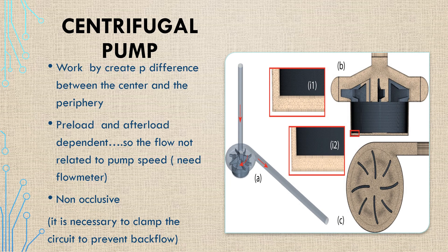The centrifugal pump works by creating a pressure difference between the center and the periphery. It is both preload and afterload dependent, so flow is not solely related to pump speed and it needs a flow meter to measure flow. It is a non-occlusive pump, so when there is pump failure or any problem, it is necessary to clamp the circuit to prevent backward flow.